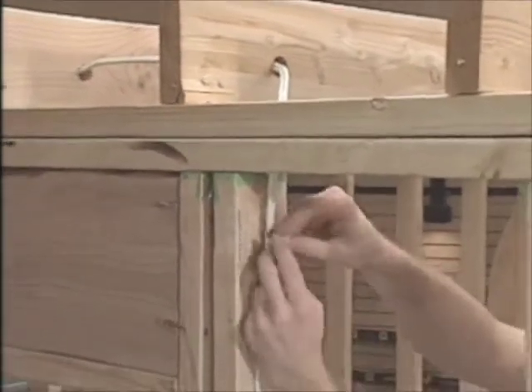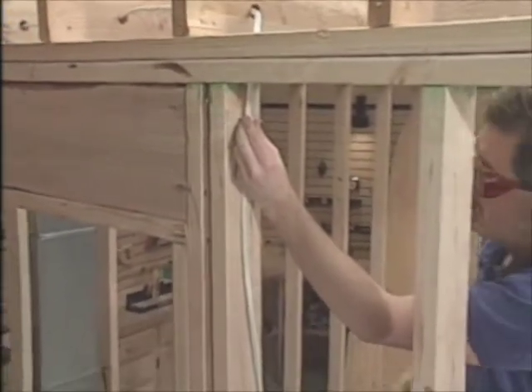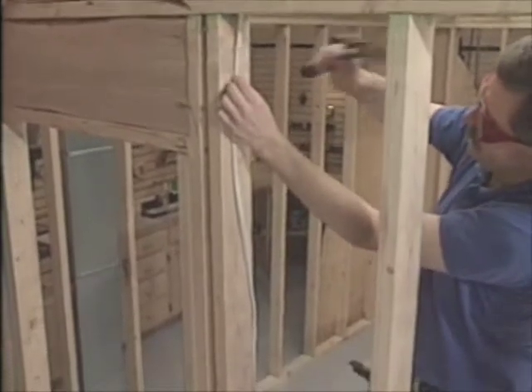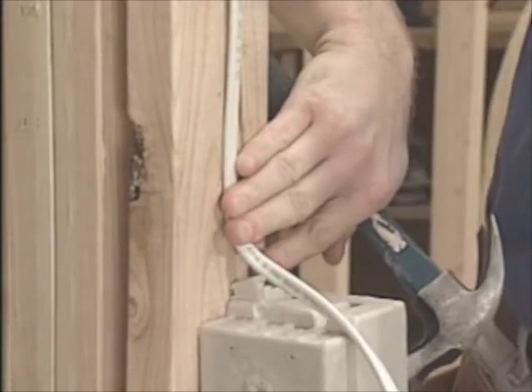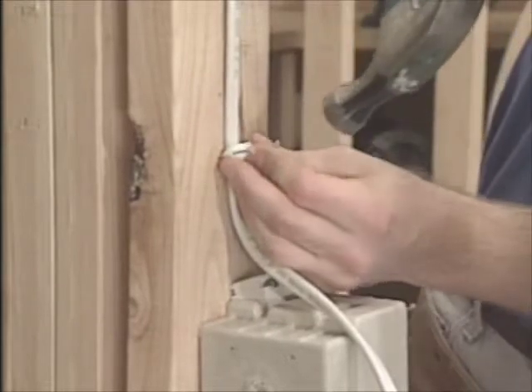Once past the door, we run the cable through the top plate, down to the switch box, and we staple it as needed along the side of the stud. According to code, the last staple before the cable hits the box should be no more than 8 inches from the box to keep the cable properly confined.